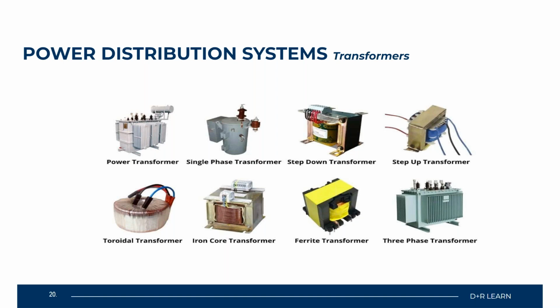So an example of this would be if you needed 24-volt control circuit voltage in your system, you can place a step-down transformer inside your control circuit, so that when you distribute that 24-volt voltage that you require on the control side, it'll be stepped down from whatever the primary voltage is. Let's say it's 120. So you can go from 120 volts on the primary side to 24 volts control voltage on the secondary side by utilizing a transformer system.